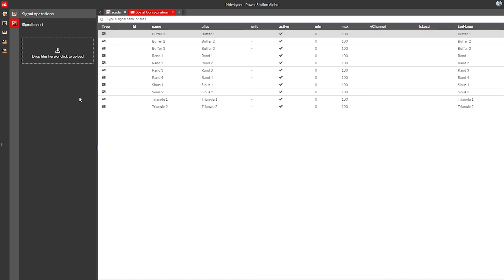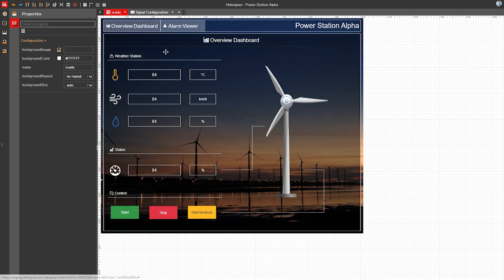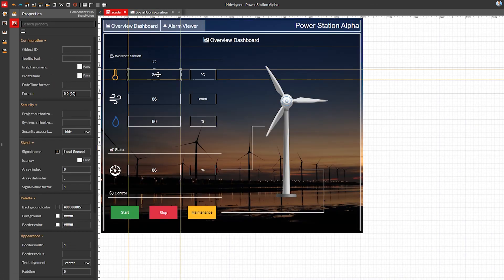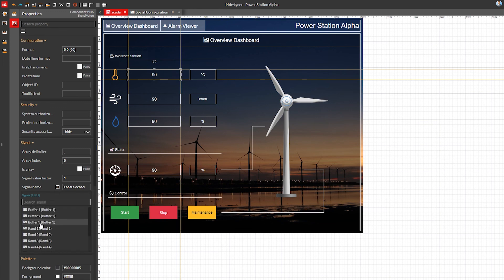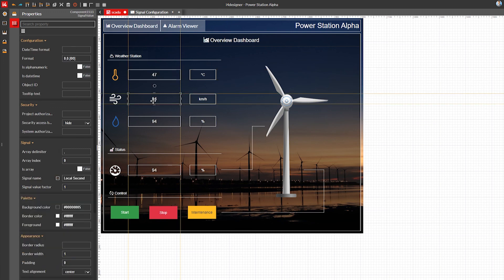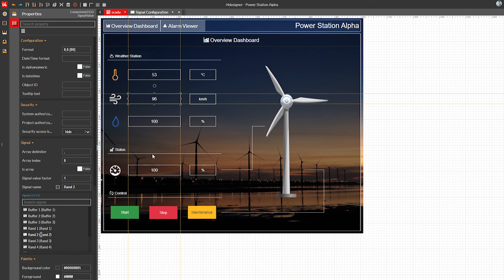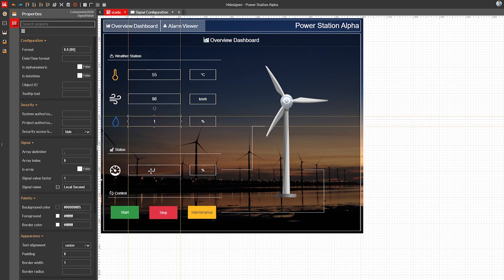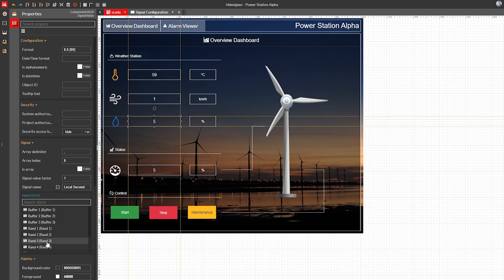Using i4scada studio we can export the signal configuration that we already have and import it in i4designer. Once that's done we now have all our SCADA signals in our i4designer project, so we can assign whichever signal we want to our components. The signal name property of our components allows us to visually select one of the signals now available in the project.